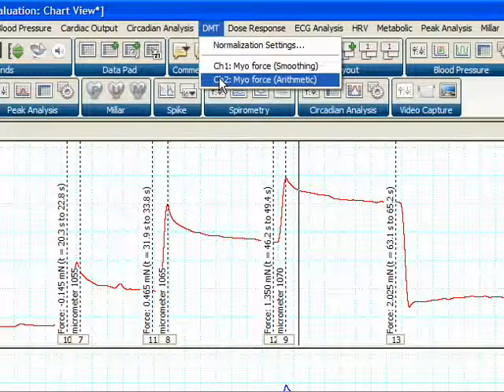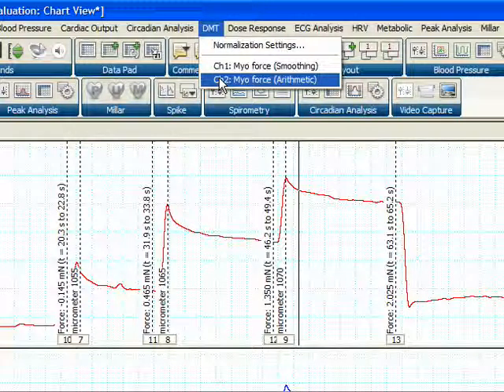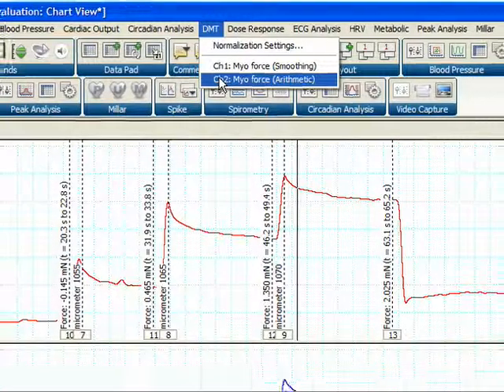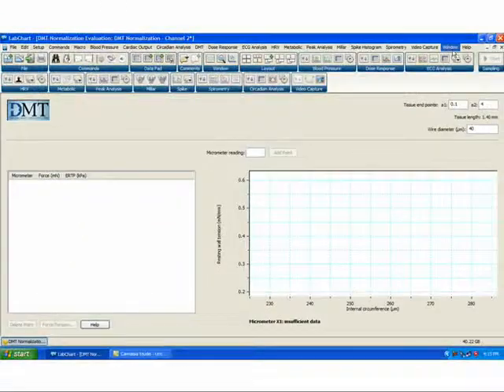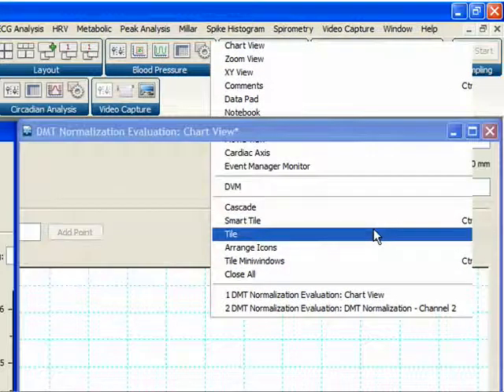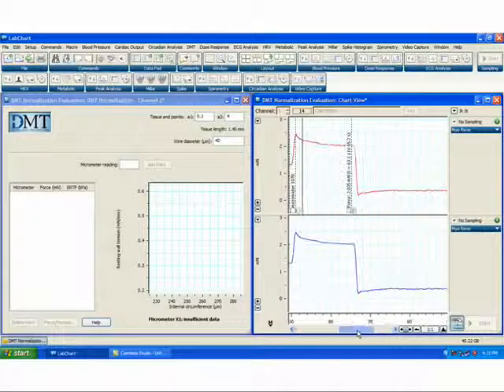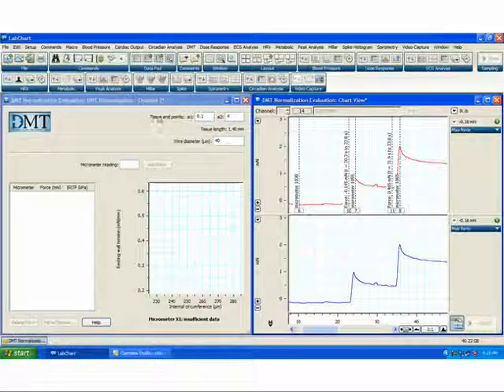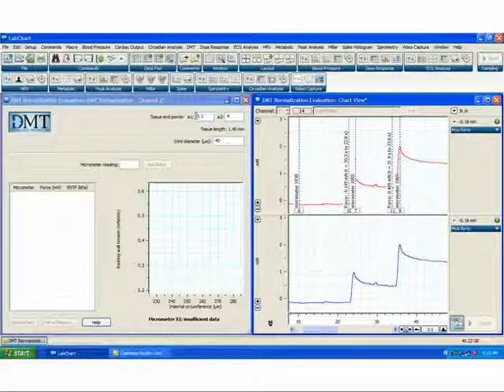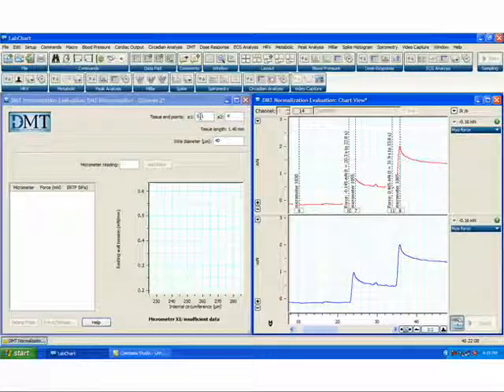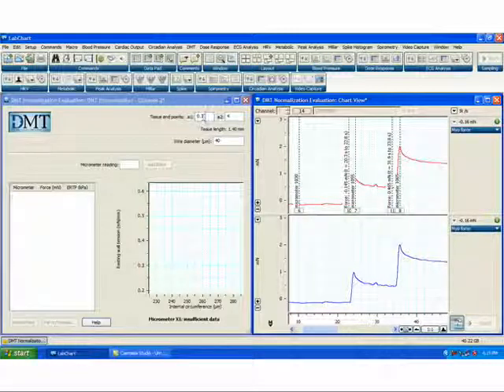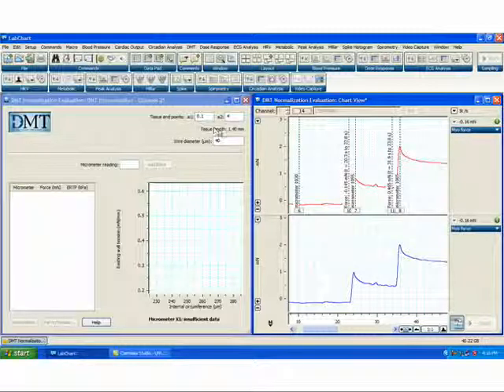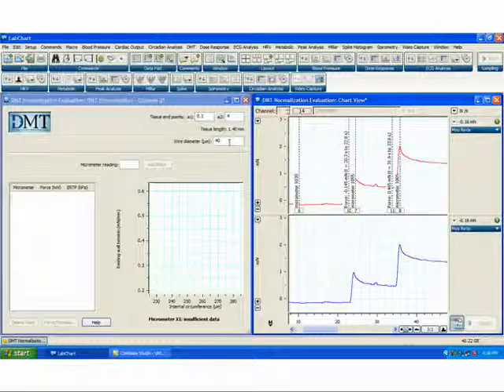Since channel 1 has already been analyzed, let's look at channel 2. To do this, I'm going to go into the channel 2 myoforce menu, and I'm going to use the window tile function so that we can view our chart data on the right-hand side of the screen, while working with the DMT menu for channel 2 on the left-hand side of the screen. The first option in the channel 2 DMT menu is the tissue endpoints. These values are entered from your calibrated eyepiece on your microscope. They are used along with your eyepiece calibration to calculate the length of the tissue. The second parameter is the diameter of the wire you are using.